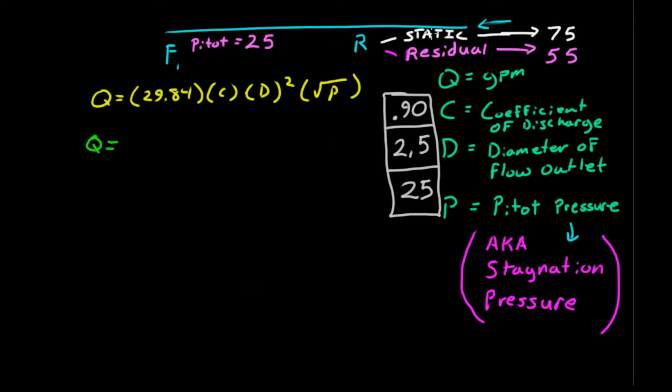Let's try the first one. We have a static of 75. We flow our hydrant and get a pitot reading of 25 while at the same time having a residual pressure of 55. A 0.9 coefficient of discharge, 2.5 inch diameter outlet, and 25 on the pitot would be entered as follows.